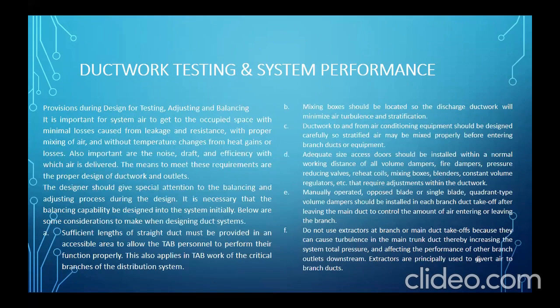Now, provisions during design for testing, adjusting, and balancing. It is important for system air to get to the occupied space with minimal losses caused by leakage and resistance, with proper mixing of air without temperature changes from heat gains or heat losses. Also important are the noise, draft, and efficiency with which air is delivered. To meet this requirement, you need proper design of ductworks and outlets. So the designer should give special attention to the balancing and adjusting process during the design. It is necessary that the balancing capability be designed into the system initially.